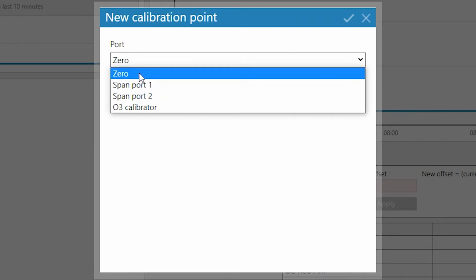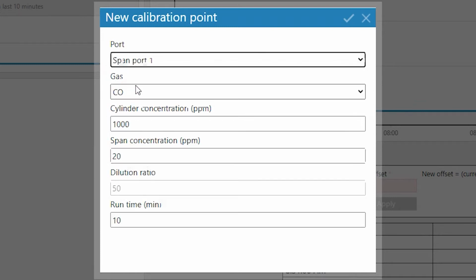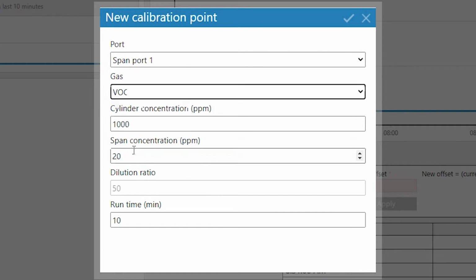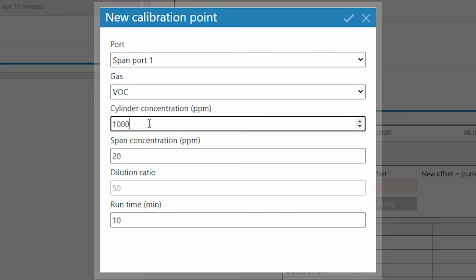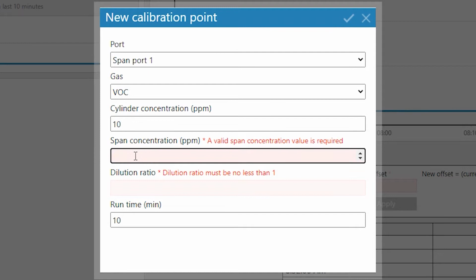So we'll select span port 1, choose VOCs. We're just going to be using a cylinder concentration today of 10 ppm. So you just want to make both of these sections 10 ppm. So this is our span concentration. So we just highlight that at 10 ppm. If your cylinder has 1 ppm, then you want these to be 1, or if it's more, whatever the concentration of your cylinder is, you need to change it here.